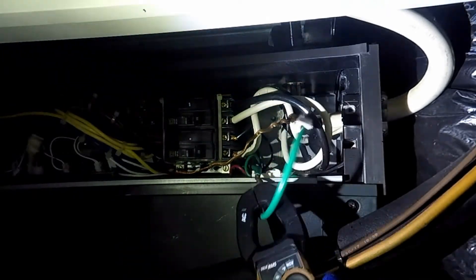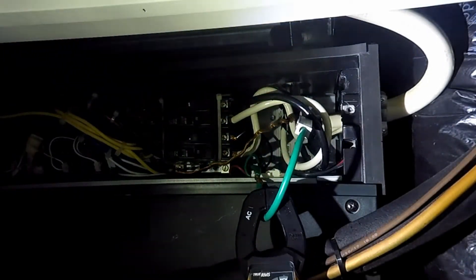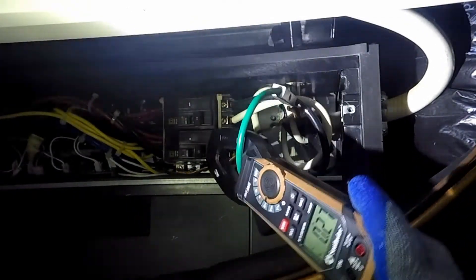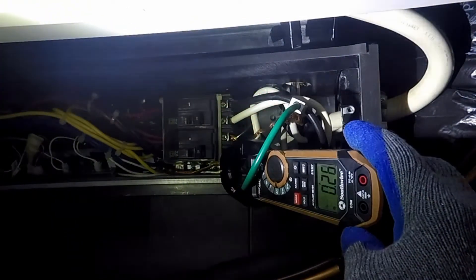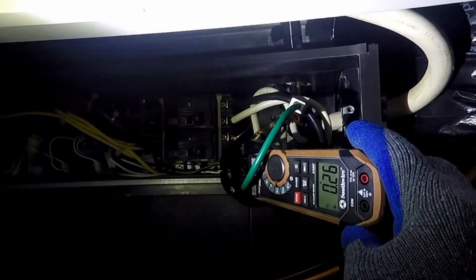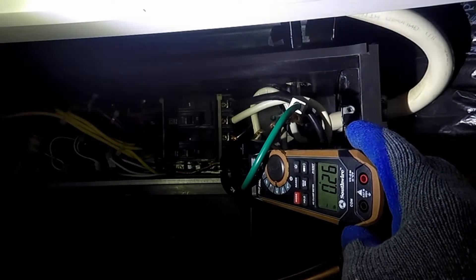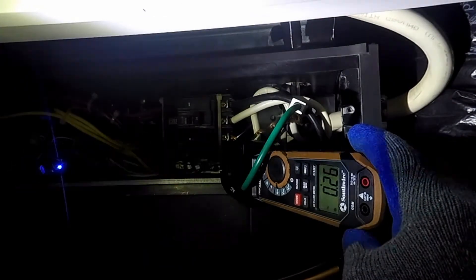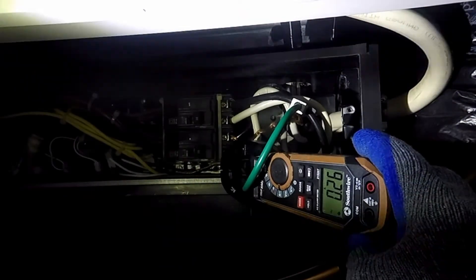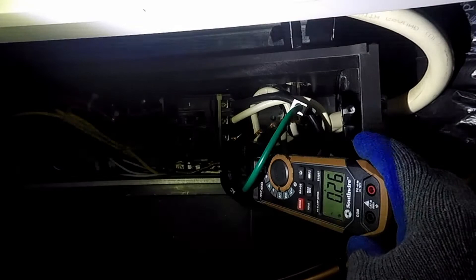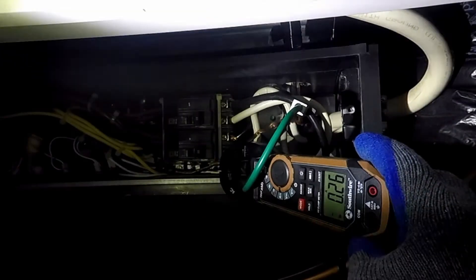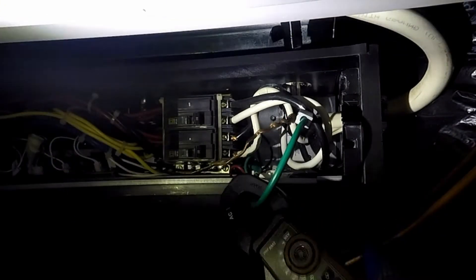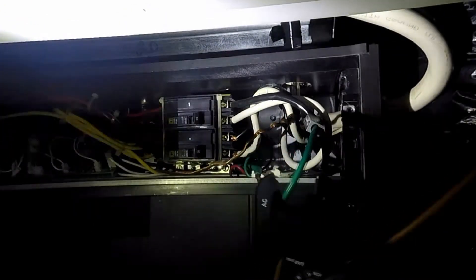An amperage reading was taken. Both ground wires had amperage of around 0.26, 0.27. There's actually no neutral wire, only two hots and the ground. This means that the ground is being used to return current to the panel.